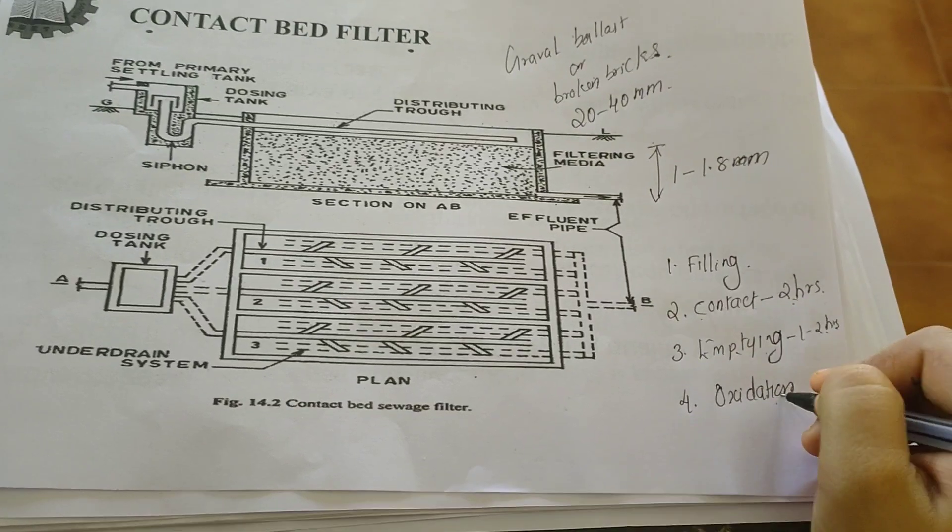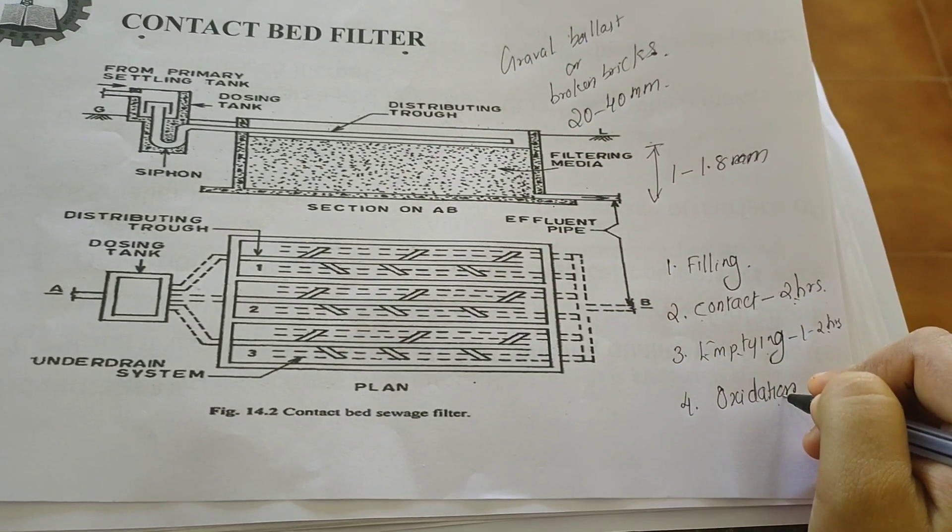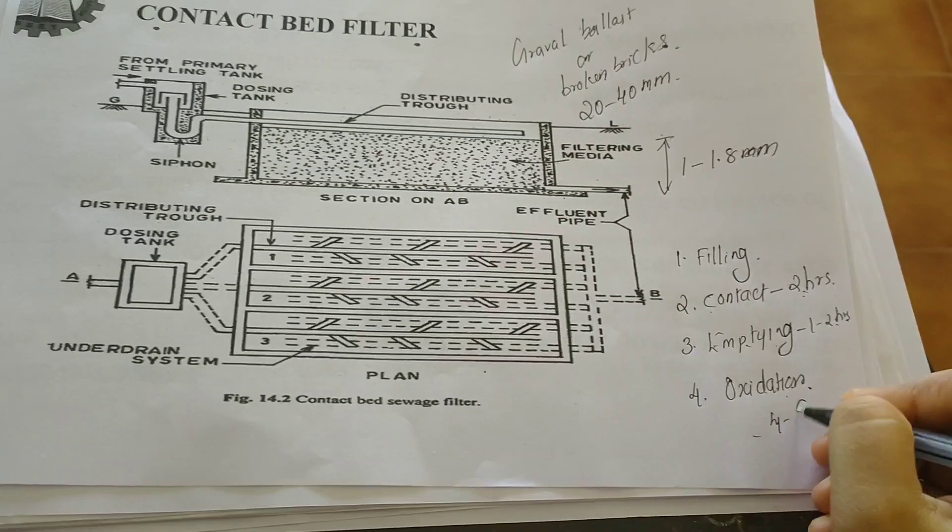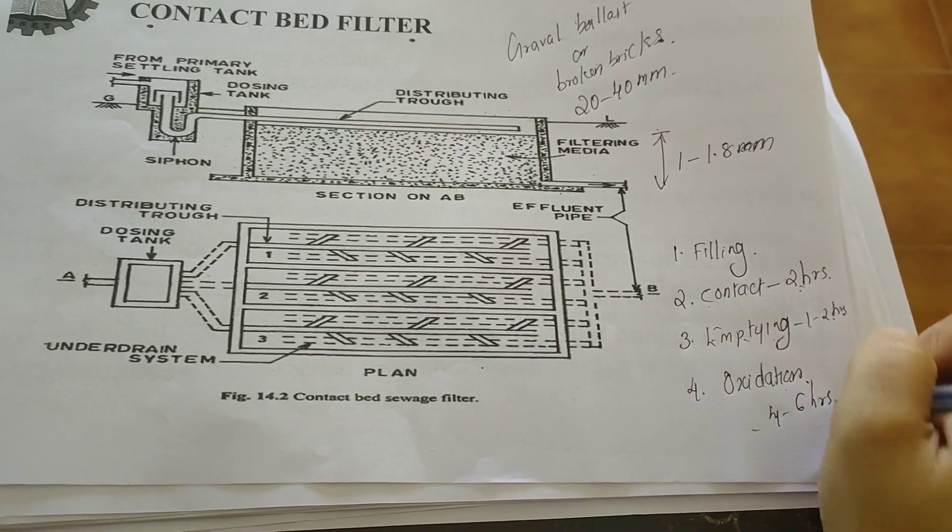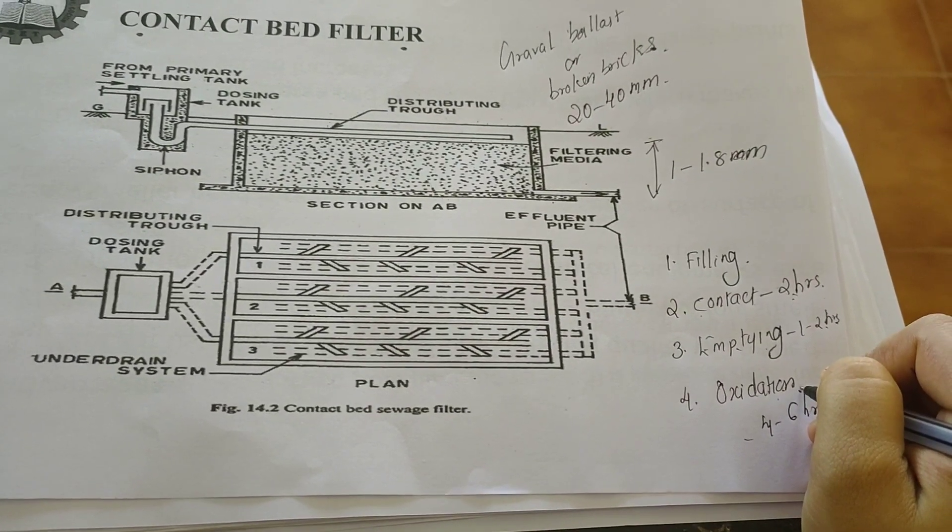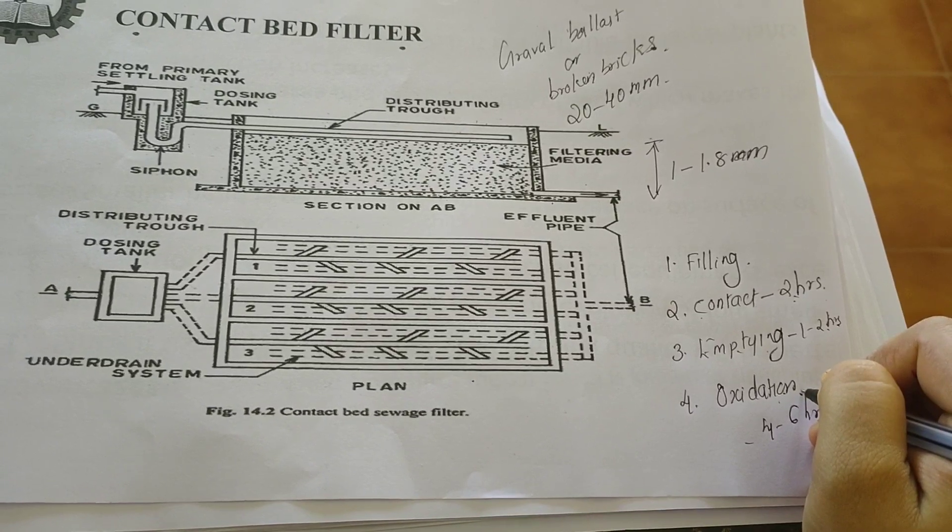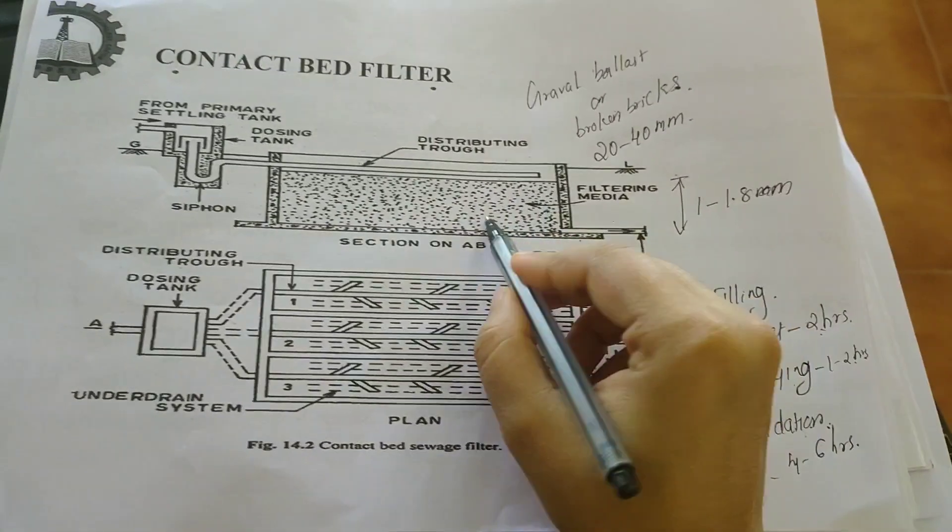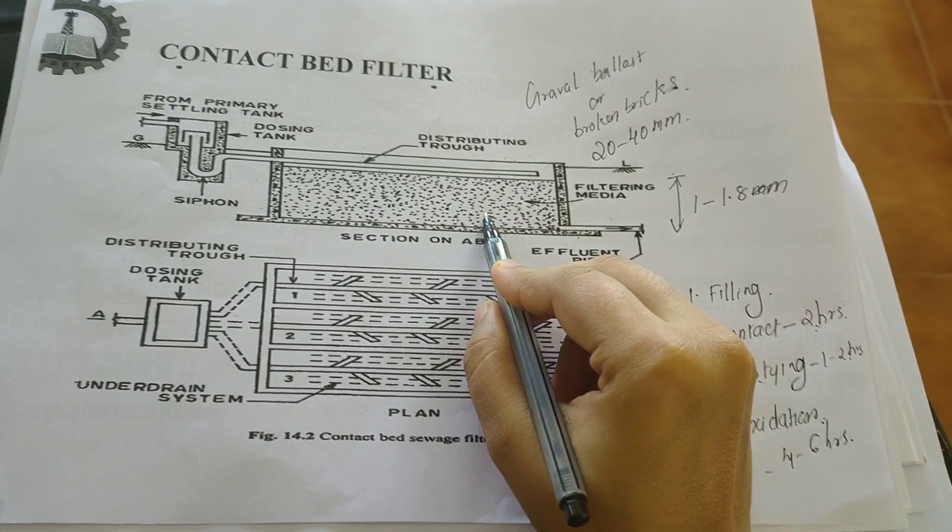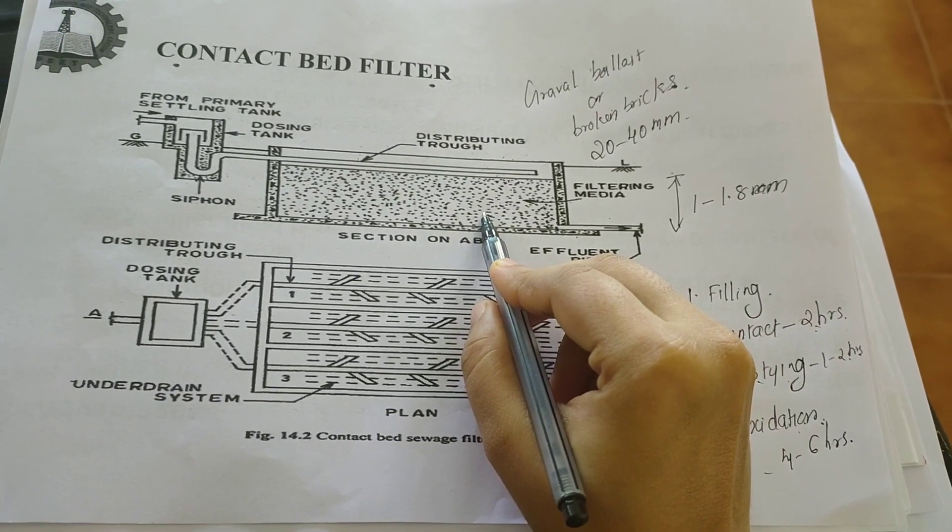Now the last phase is oxidation. In this, the contact bed stands empty for about 4 to 6 hours. This is known as the second contact period. In this rest period, atmospheric oxygen enters into the voids of the filter media. This oxygen will be used for the decomposition of organic matter by aerobic bacteria.